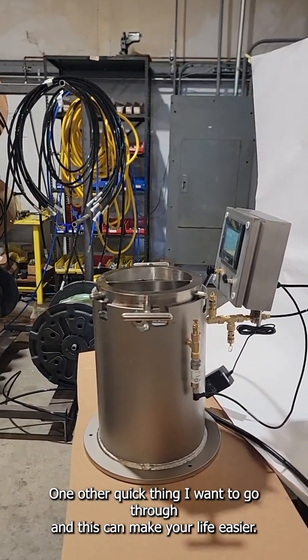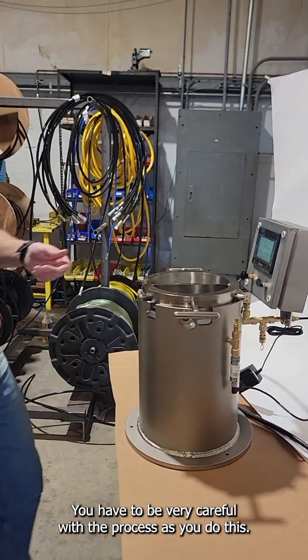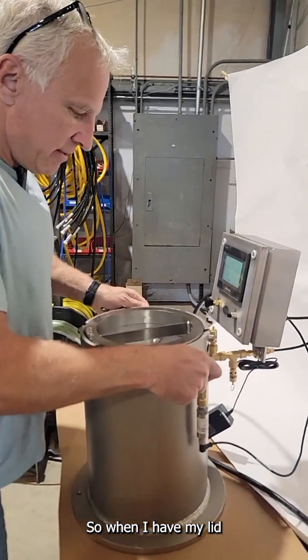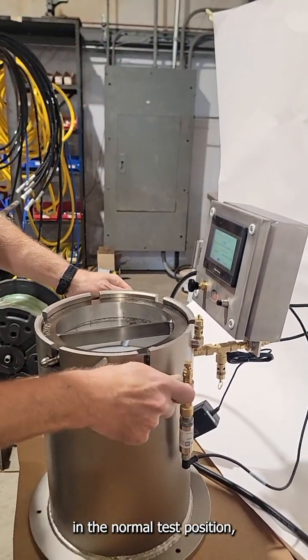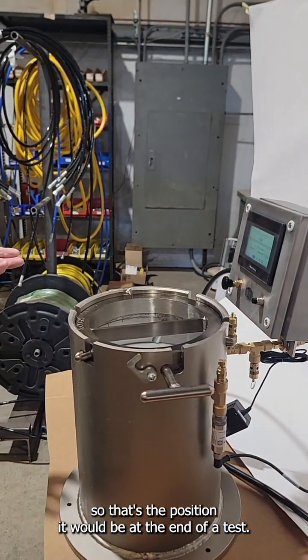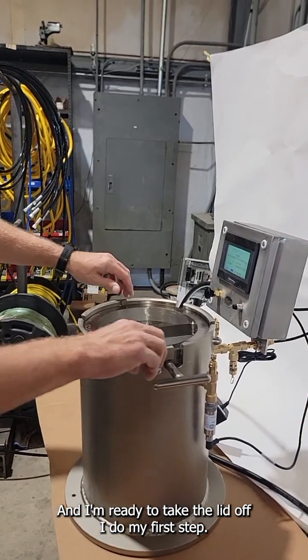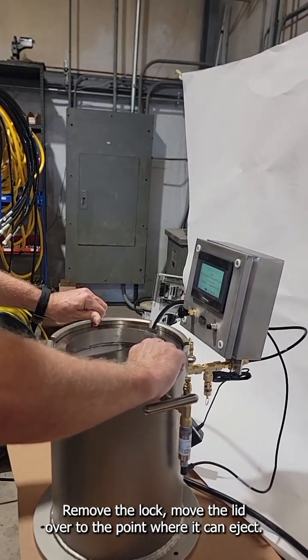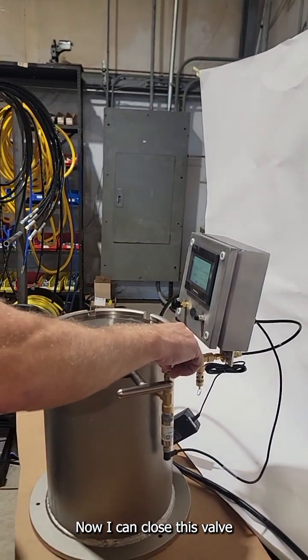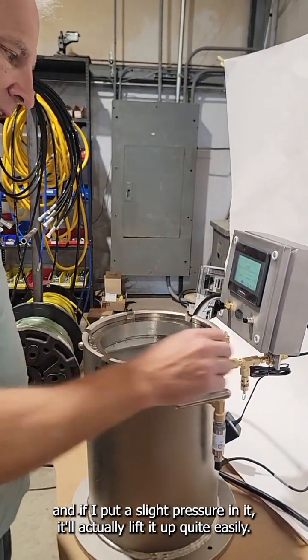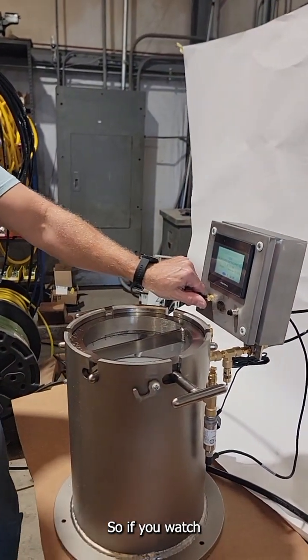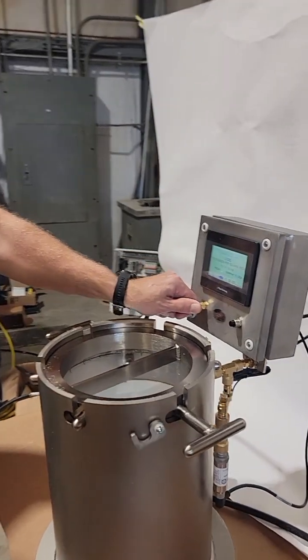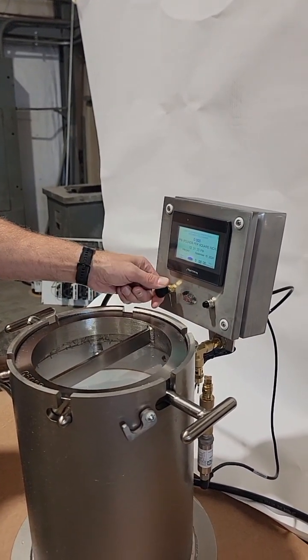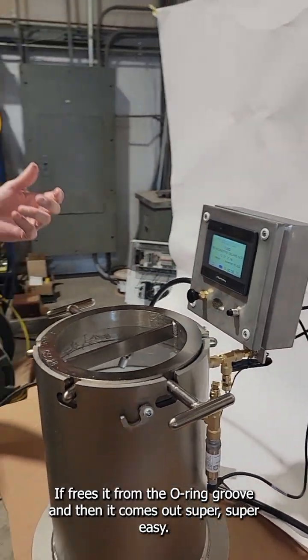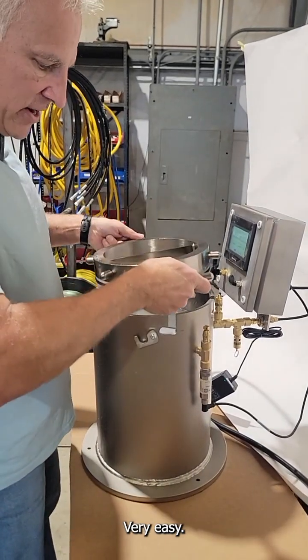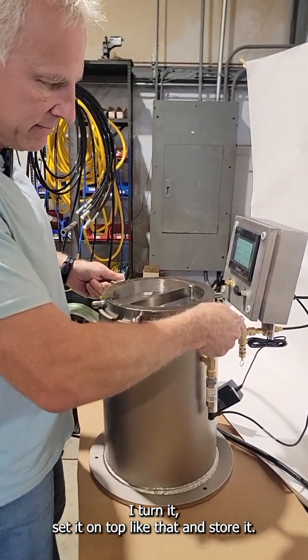One other quick thing I want to go through, and this can make your life easier. You have to be very careful with the process as you do this. When I have my lid in a normal test position, the position it would be at the end of a test, and I'm ready to take the lid off, I do my first step: remove the lock and move the lid over to the point where it can eject. Now I can close this valve, and if I put a slight pressure in it, it'll actually lift it up quite easily. If you watch the lid and the display at the same time, you can see I just give it a little pressure and the lid moves up. It frees it from the O-ring groove, and then it comes out very easy. And I turn it, set it on top like that, and store it.